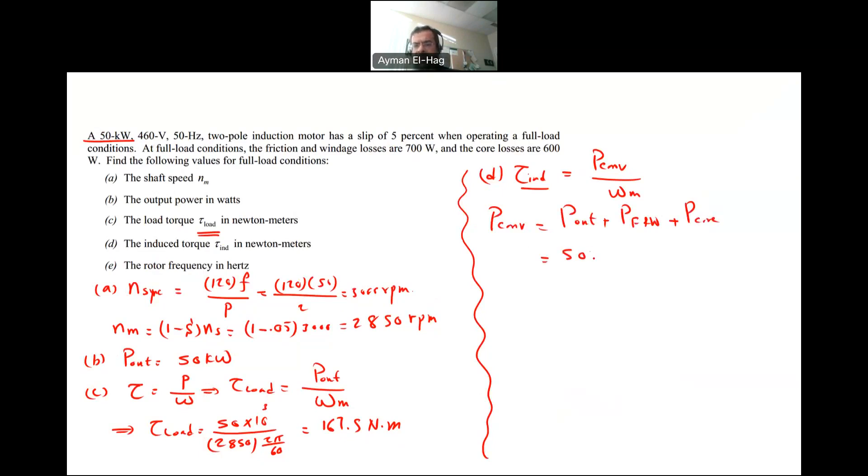I want to find what is the P convert, which is equal to the P out plus the P friction and windage losses plus the P core losses. This is 50 kilowatt. The friction and windage, it is 0.7. The core is 0.6, so we have total of 51.3 kilowatt.